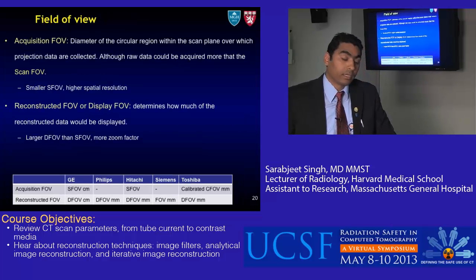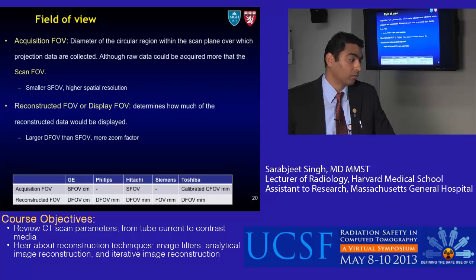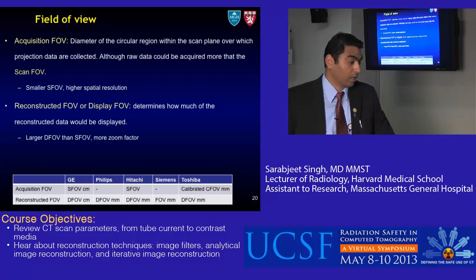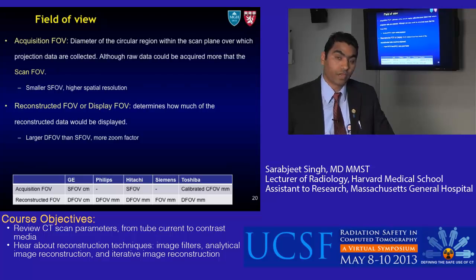The next parameter is field of view. Acquisition field of view is the diameter of the circular region within the scan plane over which projection data are collected — the raw data can be acquired beyond the scan field of view. A smaller scan field of view gives higher spatial resolution. The reconstructed field of view, or display field of view, determines how the reconstructed data is displayed. If the display FOV is larger than the scan field of view, the zoom factor is greater than one, and the images become blurred as zoom increases.